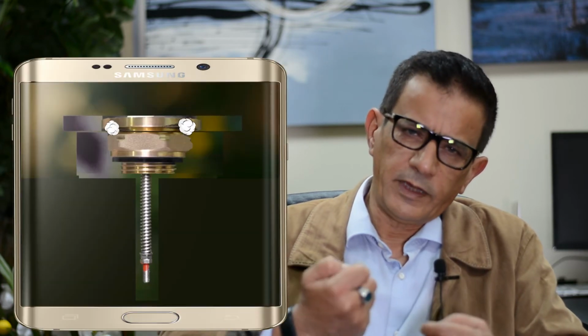So, back to the pressurized vessel concept. This transformer is not a pressurized vessel. This PRV, pressure relief valve, is to keep the pressure inside the transformer the same as the outside atmospheric pressure. Whenever there is excess pressure inside the tank, it provides a force which moves the rod against the spring force and releases these extra gases. As we explained earlier, there is an air cushion above the oil level in the transformer. During faults and abnormal conditions, extra heat is generated inside the transformer. So this air, this gas inside the transformer, will get heated.